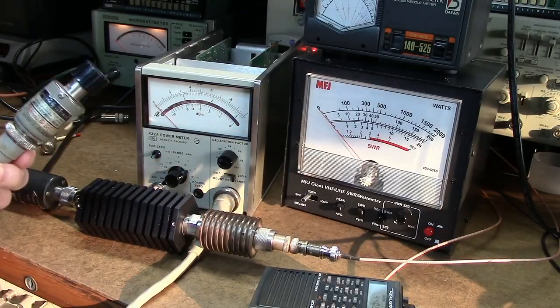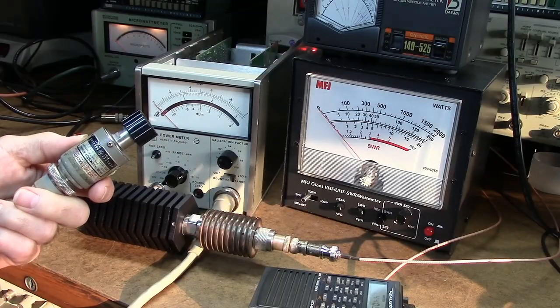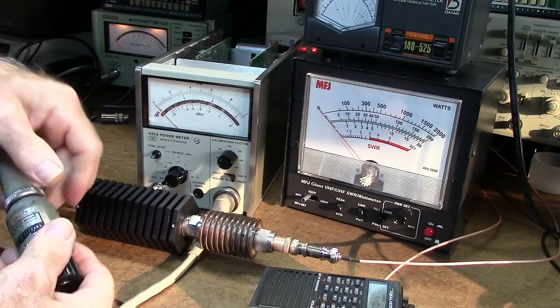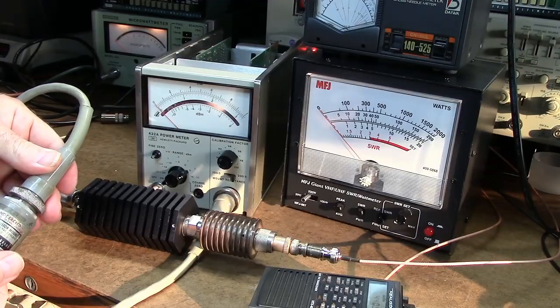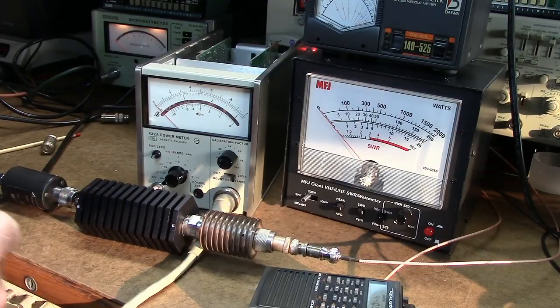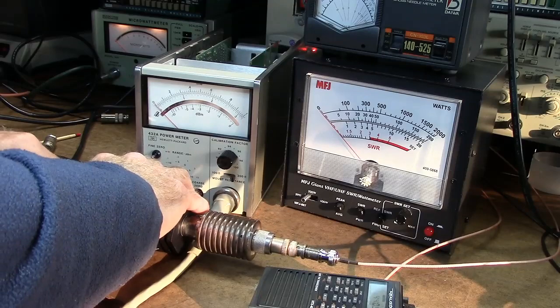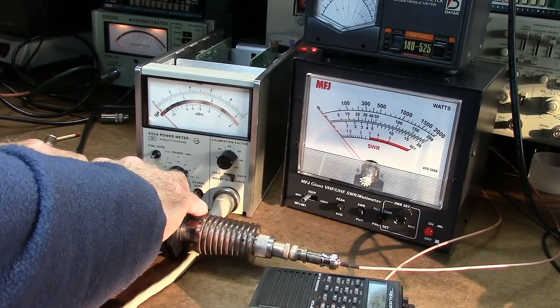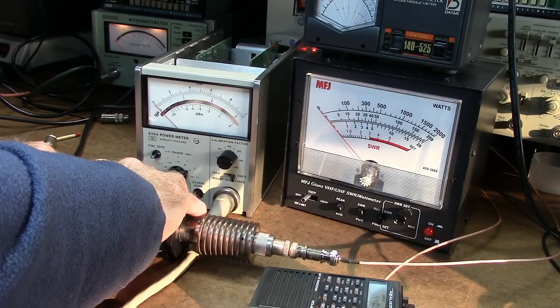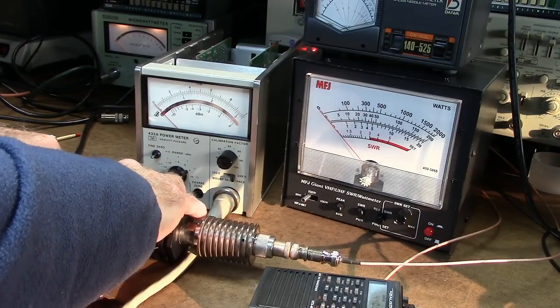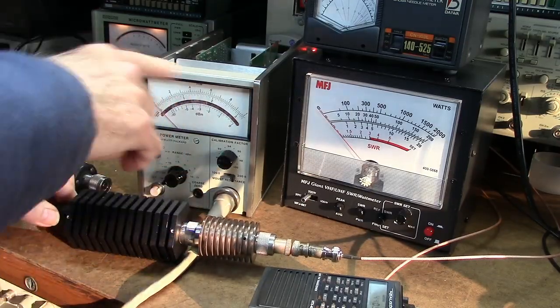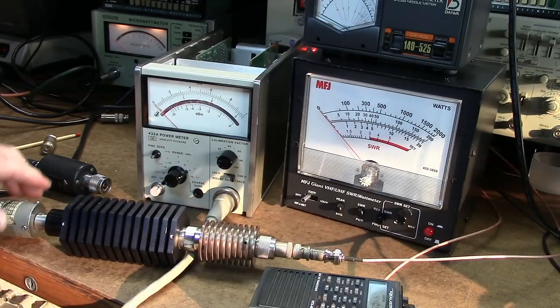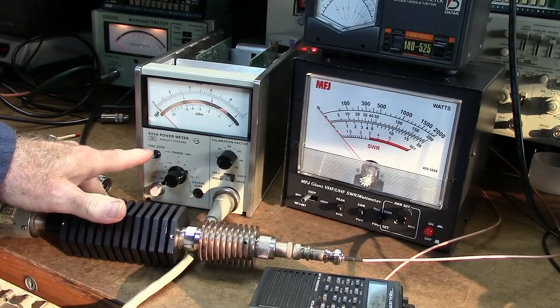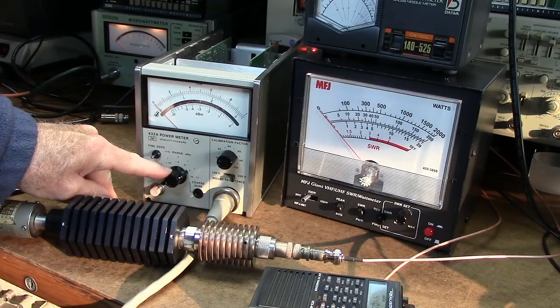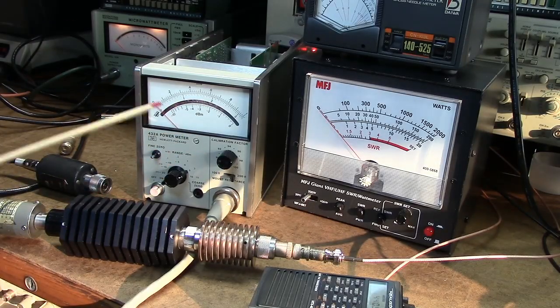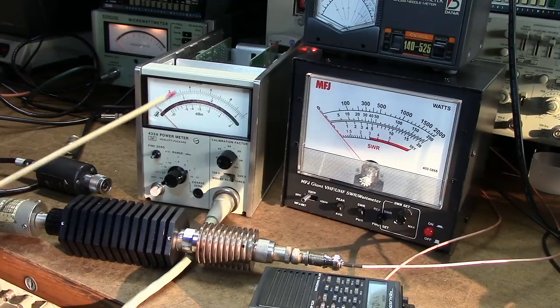And here's the thermistor mount here. This is the 8478B. So I'll connect that to the series connected attenuators, which will reduce my signal by 1,000. Always want to use attenuators. You'll blow these meters up if you transmit into them. I've already gone through the calibration of the 432A. It's on the 3 milliwatt full scale, so this would be 3 milliwatts, 2 milliwatts, 1 milliwatt.